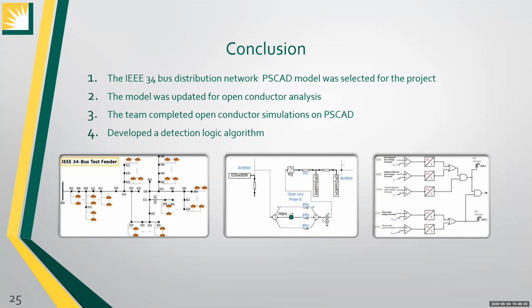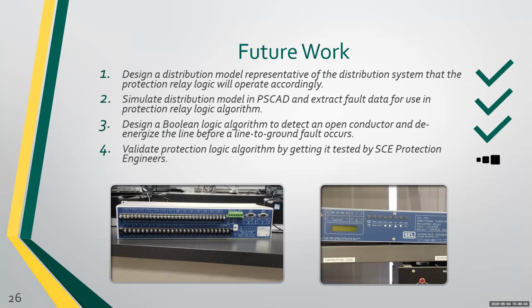We as a team completed many of the deliverables for the project. However, due to COVID-19, there is one item that still needs to be done: validating the detection logic. To do this, we would need to submit our detection logic to our liaisons at Edison to be tested. Based on their feedback, we would make any adjustments to our trip equation. If the logic was validated or approved, we would then program the trip equation into the SEL 351 relay to determine the probability with which the relay could detect an open conductor using our logic.